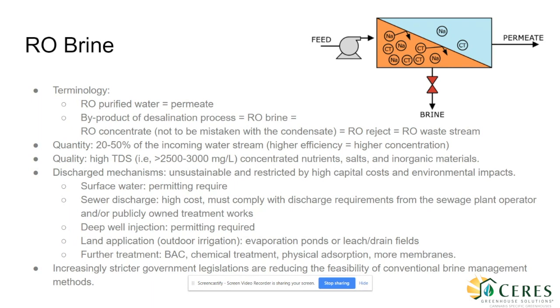Additionally, this stream will be highly concentrated with salts, nutrients, metals, and other inorganic materials. Municipalities often consider this stream a toxic liquid. Because of this, discharge of this stream can be very difficult. For example, discharging may require permits, further treatment, or additional infrastructure requiring a lot of space — all of which come at a high cost. Additionally, this brine can wreak havoc on the local environment and disposal infrastructure. In addition to these burdens, RO systems have a very high operational energy demand.